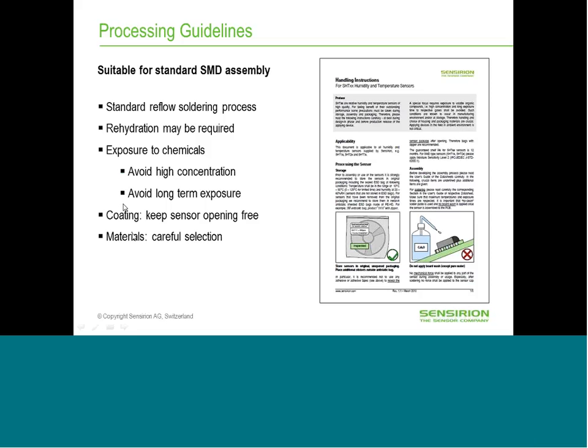Coating is always a topic, so conformal coating can be applied, no problem, but you have to make sure that the sensor opening stays free of the coating. Otherwise the sensor will not measure anything anymore. Generally, materials that are in contact with the sensor, like housing materials or packaging materials, should be selected such that they do not have too strong outgassing of chemicals which could influence the sensor.